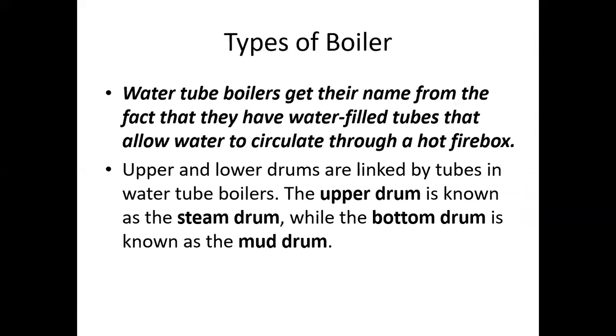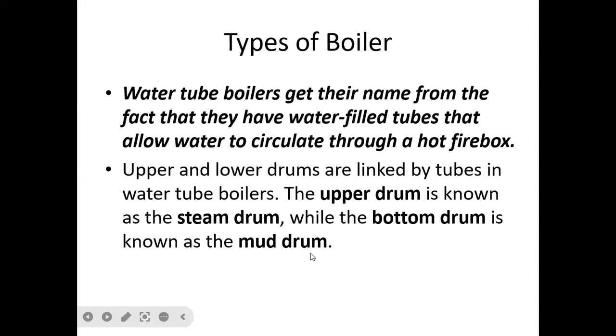There are two types of boilers: water tube boilers and fire tube boilers. Water tube boilers get their name from the fact that they have water-filled tubes that allow water to circulate throughout a hot firebox. Upper and lower drums are linked by tubes. The upper drum is known as the steam drum and the bottom drum is known as the mud drum, because solids and sludge settle there.